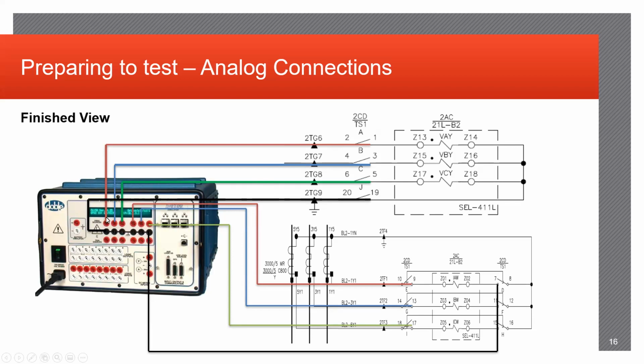Starting with the voltage sources, these are usually pretty straightforward to hook up. Once you've correctly isolated your knife switches and there's no other voltage source going into your relay that you're going to be testing, you'll just directly plug in your A, B, and C phase voltages straight into the relay, making sure you also have your reference back to ground. The currents get a little bit trickier, however, mostly because the way current works, obviously, is it's a flow state.